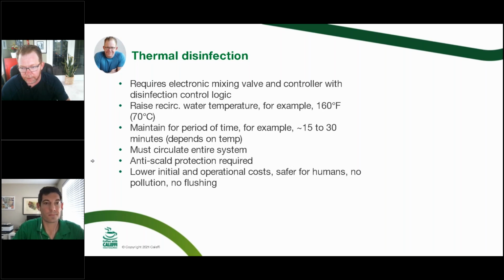Obviously, it has to circulate through the entire system. It's the same discussion we have with indirect tanks, where we don't hold indirect tanks at 100 or 120 degrees because we don't want that bacteria to grow. So it has to circulate through the entire system. And again, to sort of beat on that issue, we have to make sure we have point of use or some other means of anti-scald to make sure we don't have any protection issues. Typically, thermal disinfection has a lower initial operating cost. Obviously, it's safe for people, which is great. There's no pollution, there's no flushing.